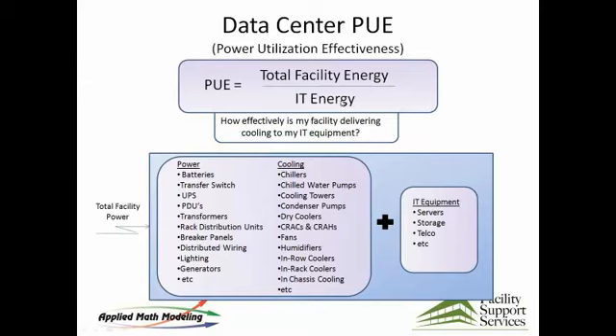Now this is the shared plenum area. This is a NOC area over here on the left. Is that correct? That's correct. And then underneath you've got a shared plenum. So you used a baffle, but it's open to the underfloor, right? Yeah. Out of that 3,600 square foot, that NOC is approximately 800 to 900 square feet of that. And you've only got an 11-inch floor.